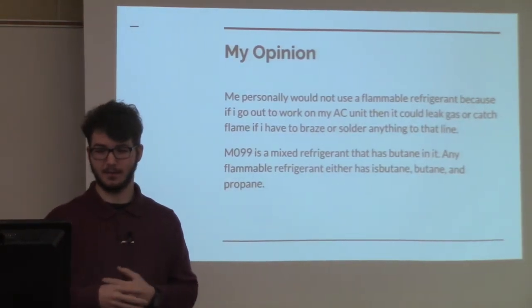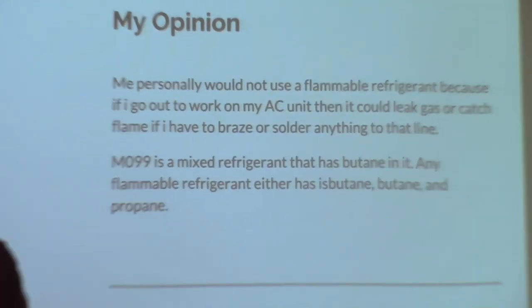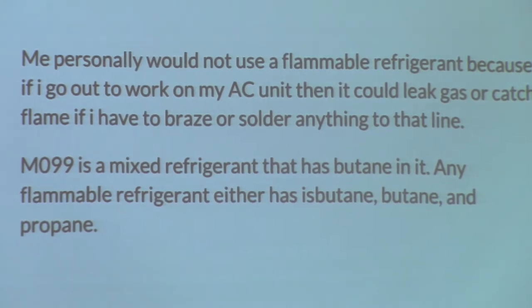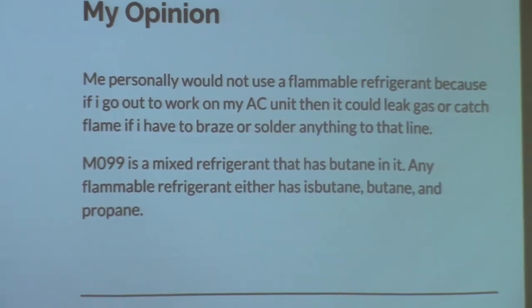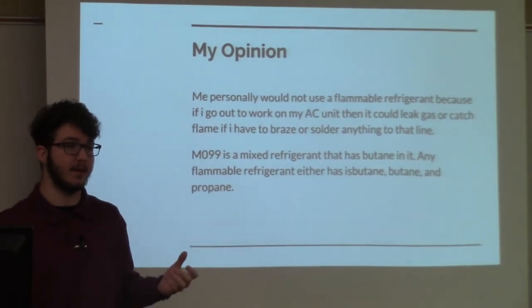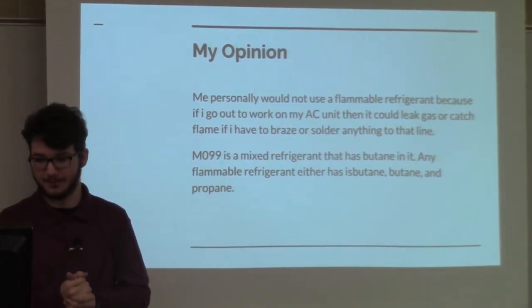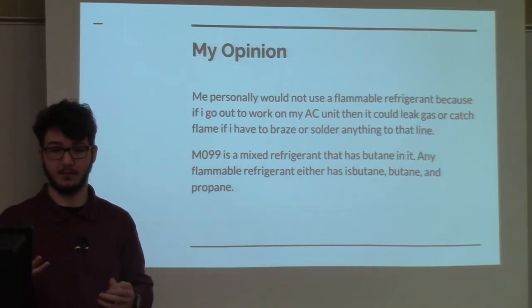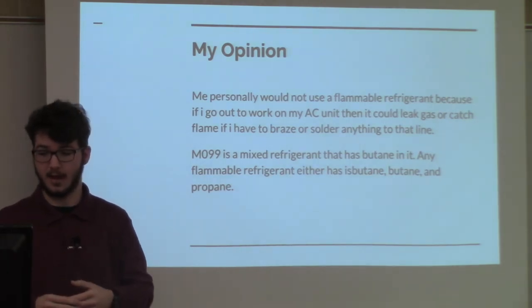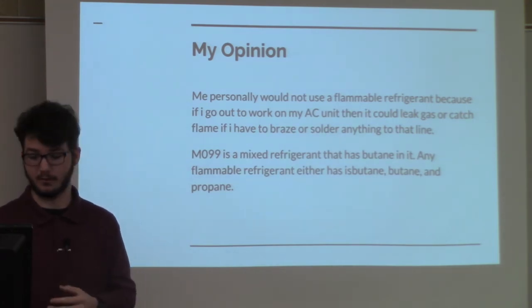My personal opinion is that I would not use flammable refrigerants in my system, vehicle, or anything like that, because of how flammable they are. You always want to check for a leak. I don't want to go to somebody's unit in the field and have to braze something and lose my eyebrows. MO99 has butane in it, and most of these mixed refrigerants — because MO99 is a mixed refrigerant — contain isobutane, butane, or propane. Those are the most common gases used in refrigerants.